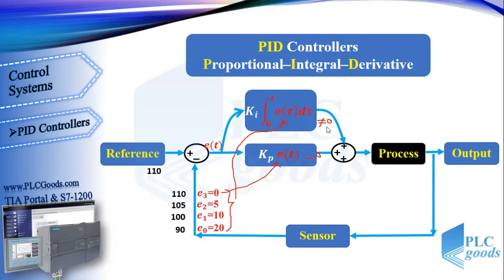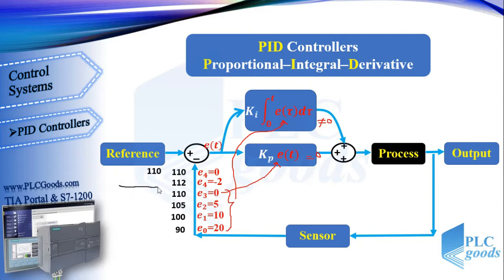Therefore, unlike the proportional controller, the PI controller can open the filling valve sufficiently even when the error is zero, so the integral term compensates for the proportional controller's weakness. The PI controller has a small problem that can be ignored in most industrial processes: when the level reaches the reference value, due to the integral term the filling valve remains open, causing the liquid level to rise again. When the error becomes negative the system returns to reference, and the integral term causes the controller output to fluctuate slightly, which disappears over time.